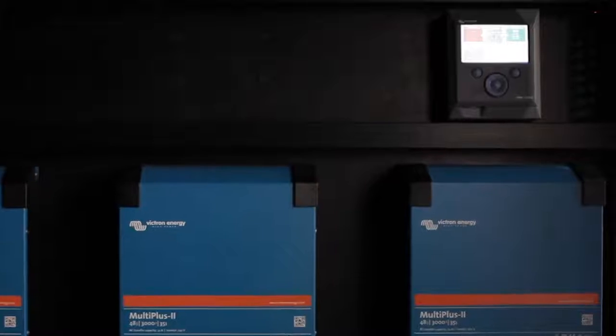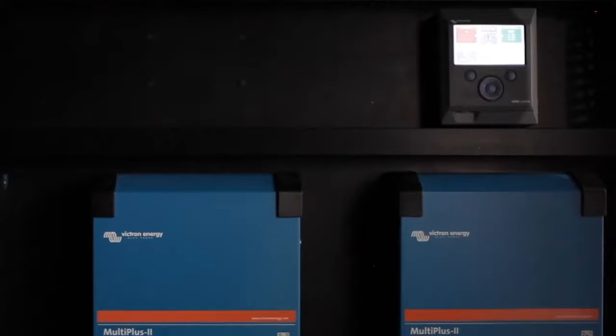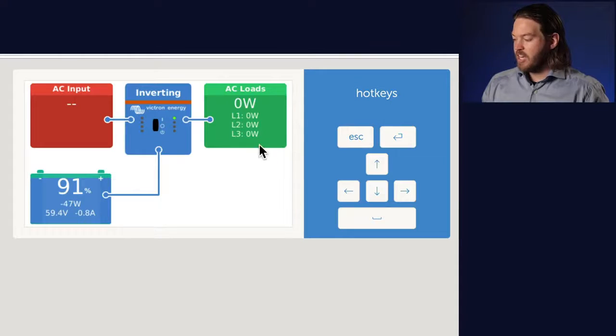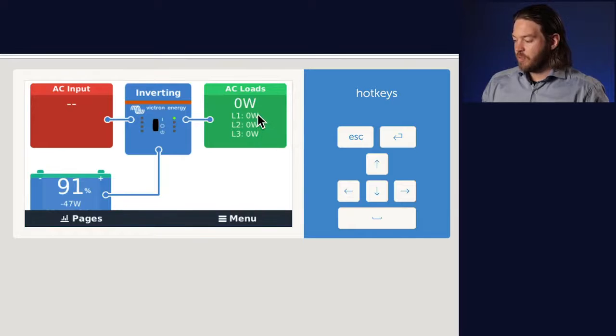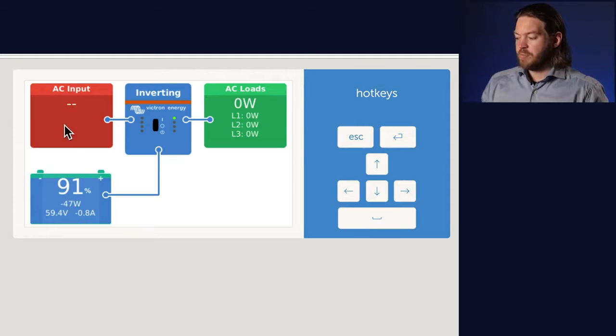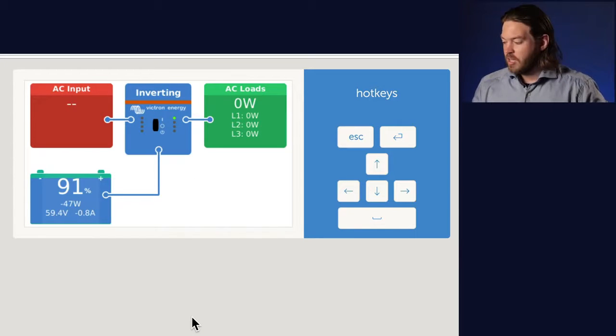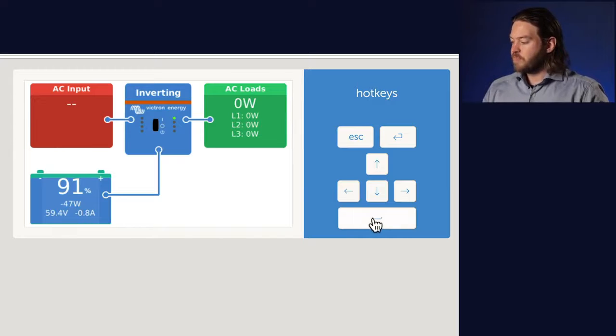I've now disconnected the MK3 to USB adapter. I've connected in my GX device, in this case color control GX, and loaded up the remote console, and we can see here now the three phases appearing under the AC loads. Now this is a basic system at the moment, there's no AC input and there's no solar charge, but for testing to make sure that this system is correctly configured, this will show us what we need to know.